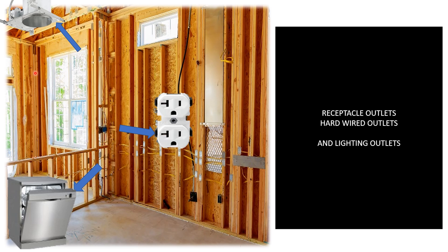If you head over to NEC 210.8, which covers GFCI requirements, it says all receptacles 125 volts or less are required to be GFCI protected. That's talking about receptacle outlets — anywhere in the system where you're attaching a receptacle, it's required to be GFCI protected. But if that same code were worded 'all outlets,' you have to be very careful — someone could read that and think it means only receptacles, but no: 'all outlets' means all types in that specific location, including lighting and hardwired outlets.